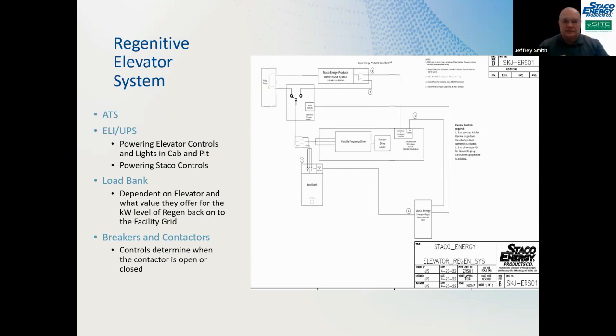The fire department, the fire marshal said, as long as there's no fire in the elevator area, in the shaft or anything like that, they want to be able to use the elevator up and down to get people out for 2 hours. Well, what happens with that is, most of the time, every elevator is worked by a motor going up and down. We won't even talk about the power factor correction that we possibly could use for this, but what happens is you've got regenerative power being sent back from the motor.